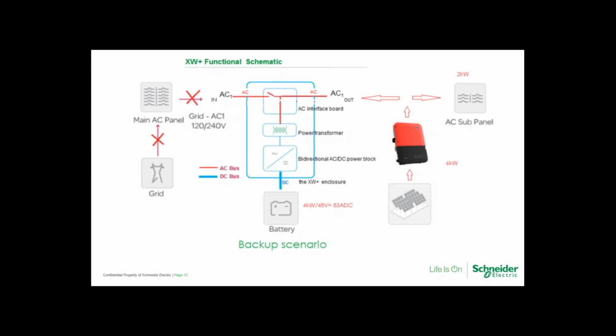And that also brings up another point as well: if you're AC coupling off grid, then you want to make sure that your battery chemistry is going to be tolerant of ramping up to bulk and then shutting down, if you're using a grid tie inverter that does not have an off-grid mode. Typically, a lithium chemistry is well suited for partial state of charge, or ramping up to a certain voltage and then stopping. They're pretty much tolerant of different charging algorithms, whereas a lead acid chemistry, many times their warranty is dependent on receiving a proper 3-stage charge regularly. So that's another thing to consider if you're thinking about designing an off-grid system.